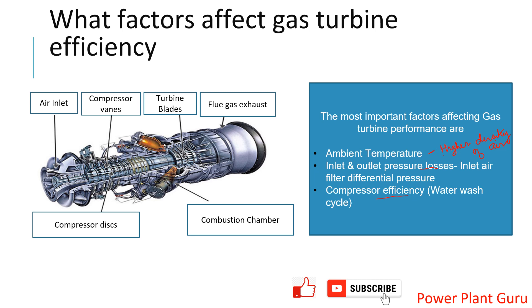Regarding air pressure coming to the gas turbine — if we have a deficiency in sucking air, for example our inlet air filters are clogged, that extra amount of energy will go into sucking the air and come out of the total output, giving you a reduction in output and efficiency. Similarly, if you have a high pressure drop at the outlet — this happens when you have an HRSG connected with the gas turbine — there is increased restriction in the flow, which also impacts gas turbine performance. That is where inlet and outlet air pressure comes into the picture.